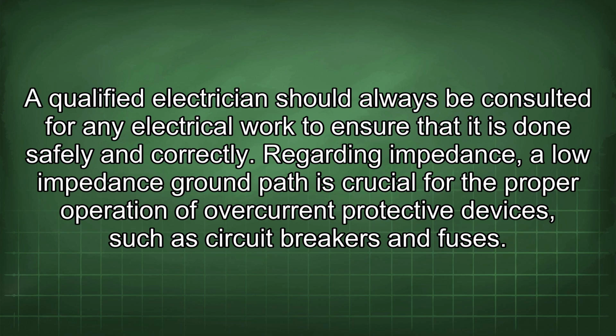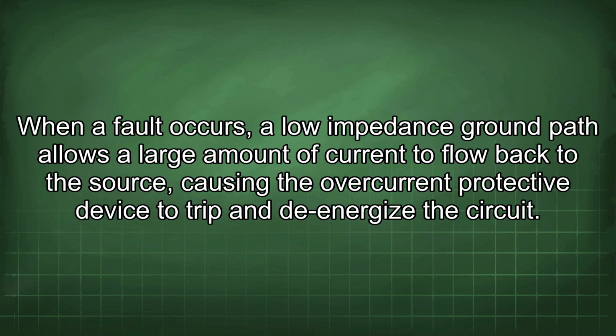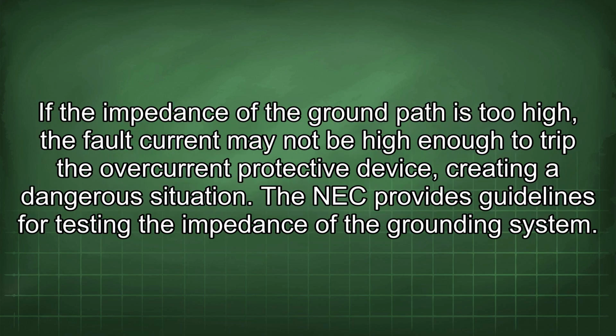Regarding impedance, a low impedance ground path is crucial for the proper operation of overcurrent protective devices, such as circuit breakers and fuses. When a fault occurs, a low impedance ground path allows a large amount of current to flow back to the source, causing the overcurrent protective device to trip and de-energize the circuit. If the impedance of the ground path is too high, a fault current may not be high enough to trip the overcurrent protective device, creating a dangerous situation.